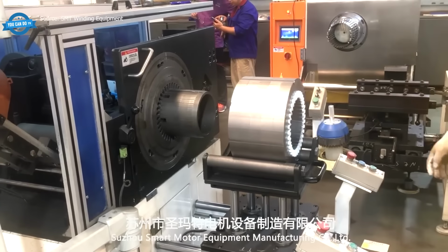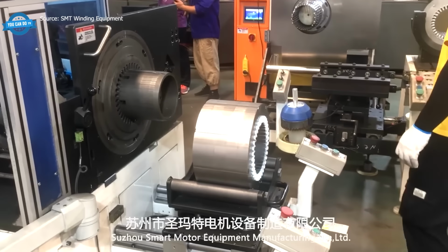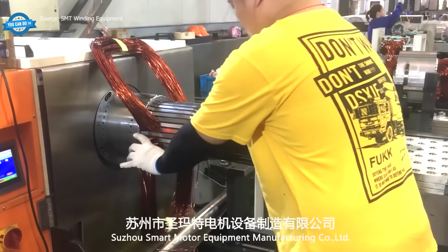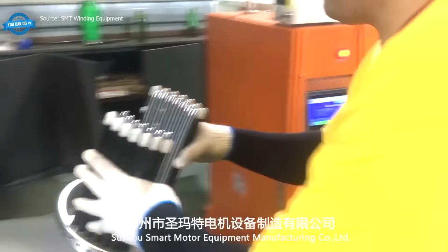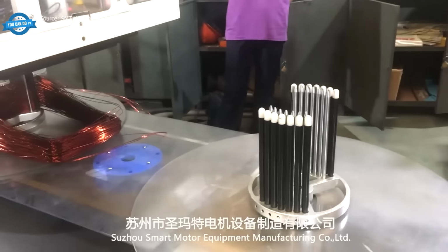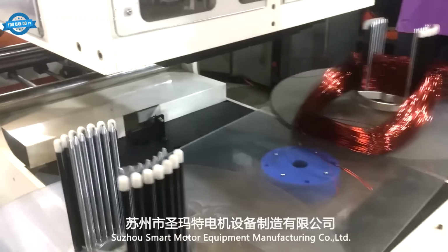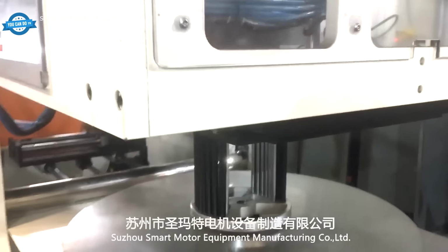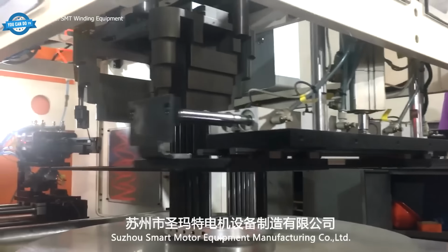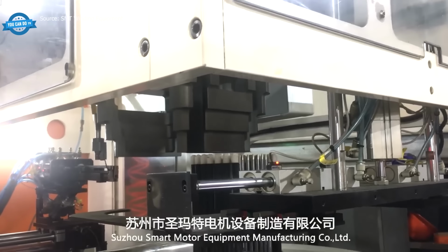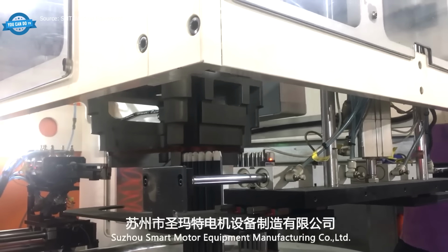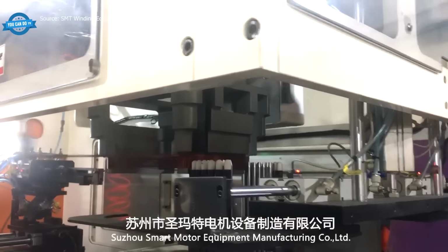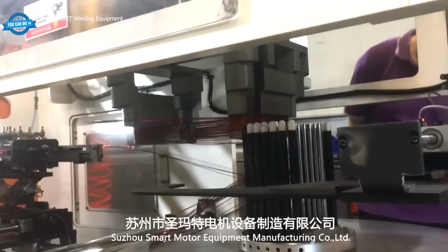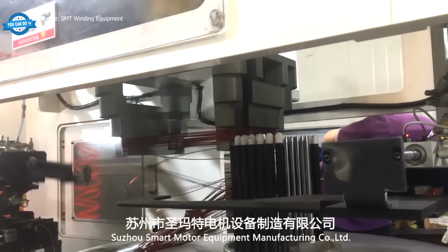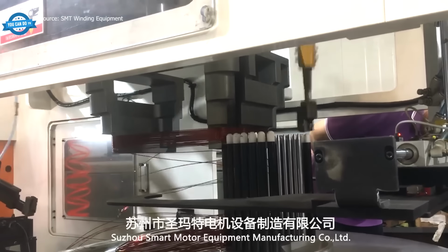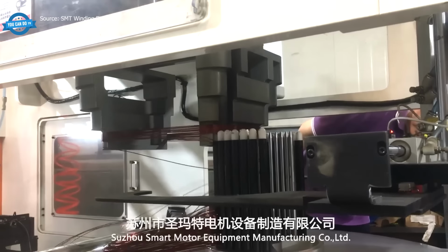A mining machine may weigh hundreds of tons, but its drive system depends on a motor built around precise control of the stator winding. Production begins with slot insulation, where automated machines insert insulation paper into every stator slot to isolate the copper conductors from the steel core. CNC winding equipment then forms copper coils and inserts them into the stator without damaging the insulation. Intermediate forming compresses the winding ends to create the space required for later operations.